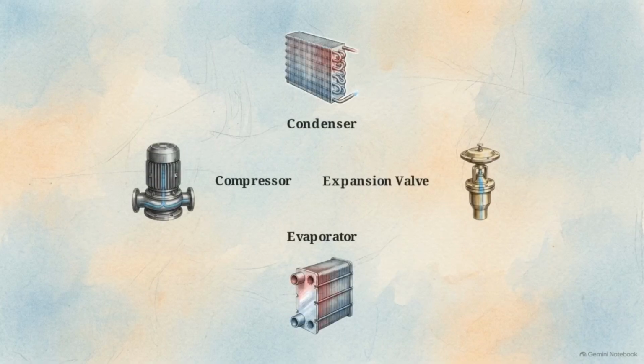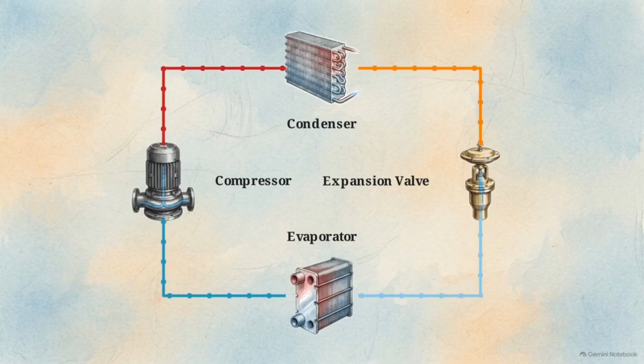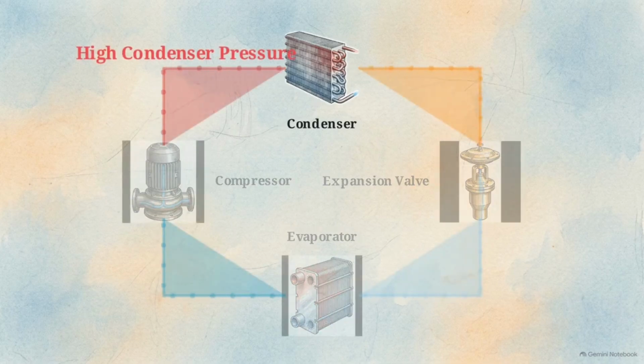In this complete diagnostic model of the loop, we can map mechanical failures directly to disruptions in the thermodynamic cycle. A warning for high condenser pressure indicates a failure occurring precisely at the heat rejection node. If airflow is blocked, or water flow is restricted, or the condenser coils are fouled with dirt, the trapped heat cannot escape. The thermal energy backs up, physically driving up the internal pressure of the entire system.